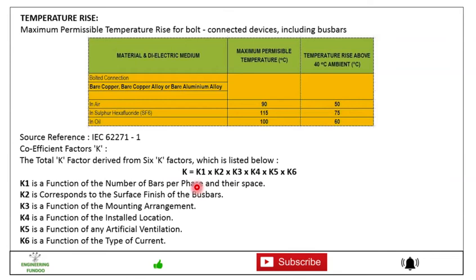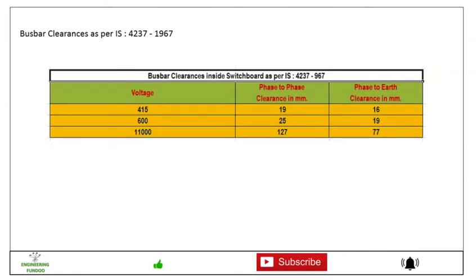Let's say coefficient factor K. The total K factor derived from 6 K factors which is listed below. So in order to calculate total K factor, K is equal to K1 into K2 up to K6, where K1 is the function of the number of the busbars per phase and their space, K2 corresponds to the surface finish of the busbar, K3 is the function of mounting arrangement, K4 is the function of install location, K5 is the function of any artificial ventilation, K6 is the function of type of current.